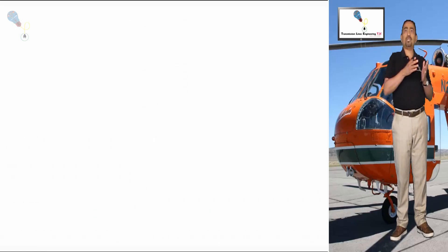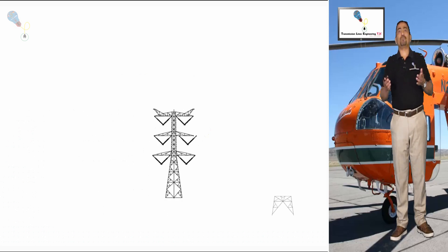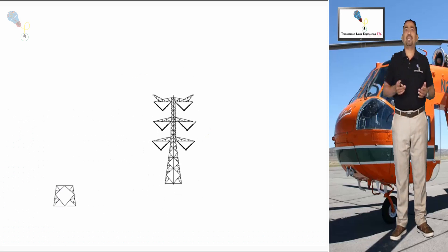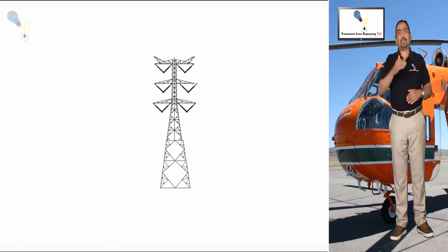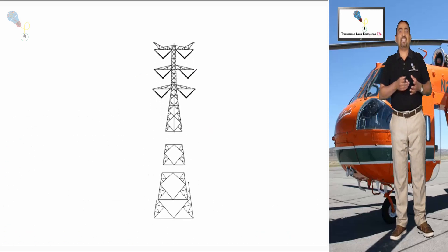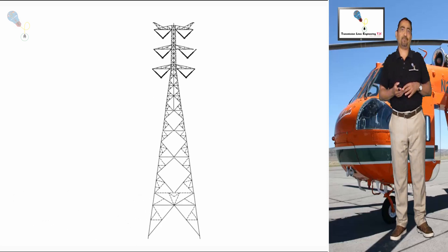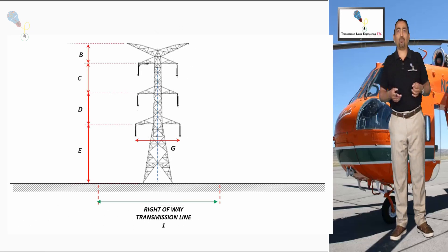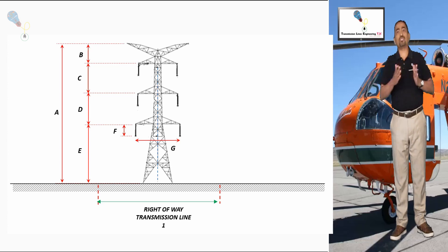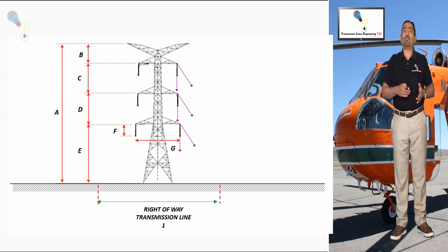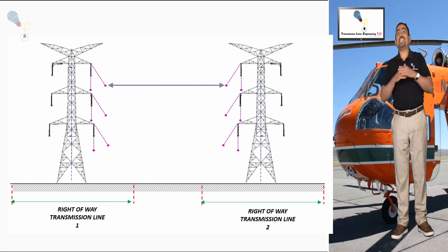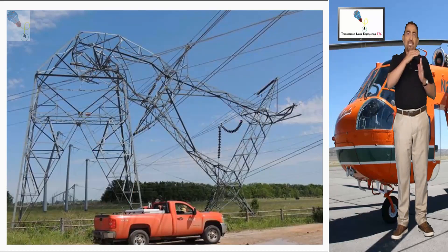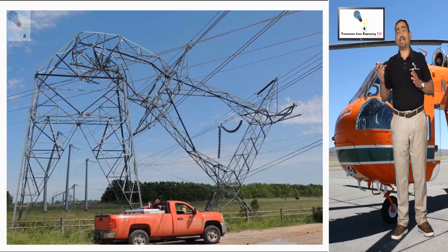As for the geometry of the suspension structures, there are different types of structures in different heights or levels. Since it is impossible to know from the beginning the maximum height of the structures to be used in our project, it is advisable to consider the tallest structure. The necessary dimensions are the very basic ones — we only require the vertical and horizontal dimensions of the cross arms. The rest of the geometry is necessary for calculations when paralleling other transmission lines, where it is common to consider that the highest structure could collapse at the waist elevation and fall on top of the adjacent transmission line.